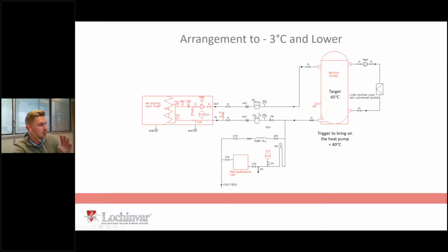And this is how we do it. So air source heat pump looks at a thermal store. The way it looks at that thermal store will be through an immersed tank temperature sensor. You'll set a target temperature on the vessel. So let's say this is a large heating system, nice oversized radiators. So our 50 kilowatt air source heat pump serving this thermal store, and we want 45 degrees centigrade. So we're going to flow from the air source heat pump at 47. And we're going to return at, well, it's a 5 degree delta T. So if we're flowing at 47, we're coming back at 42. Air source heat pumps typically work on low delta Ts. It will be a 5 degree delta T on your primary.